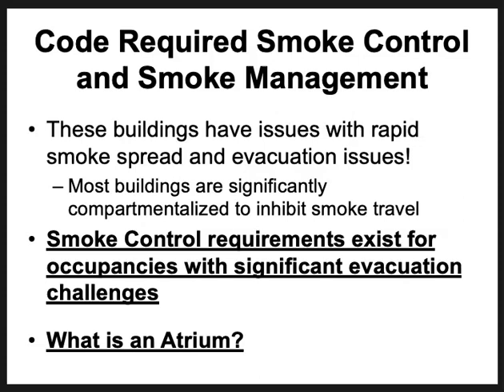Now, most buildings are significantly compartmentalized to inhibit smoke travel. That's why it's very rarely allowed to have openings from one floor to the next other than a stairwell, and usually in commercial buildings there are always doors on the stairwells. We do that to inhibit smoke travel. But many buildings, like the ones we just mentioned, do have openings from floor to floor. So smoke control requirements exist for those occupancies that have significant evacuation challenges. Think about I-3. It might not be built like an atrium, but we don't want to just open the prison doors and let everybody escape. So there are evacuation challenges. If they have a fire, they have a certain way of evacuating people, and they're going to do it in a controlled way. They need more time.